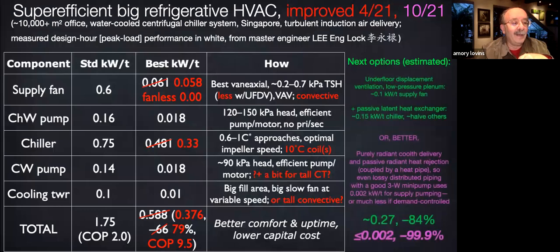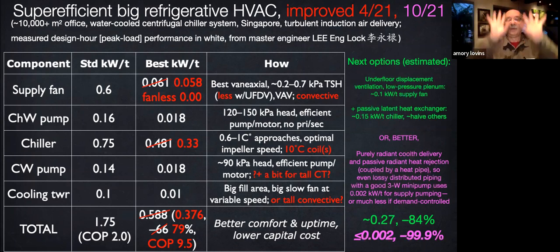Okay, even more radically, add the magenta type. Radiant coolth delivery, like we saw in the Singapore experiment, plus passive radiant heat rejection, with special surfaces that reject the heat to the night sky, even the day sky, even the cloudy sky. Even if you needed an efficient mini pump circulating cool water to radiant panels rather than coupling everything with heat pipes, you could probably still cut the total cooling power of the whole system to roughly 1/1000th of standard practice, with much lower capital cost. Or if the radiant cooling panel inside and the passive radiator outside are passively connected, so you don't need the little pump, then the electricity used is zero. Let's try it. What are we waiting for?